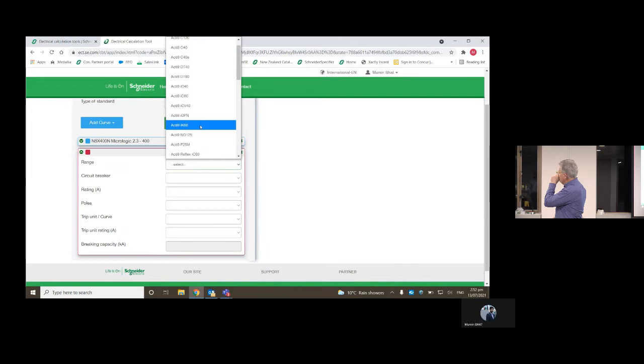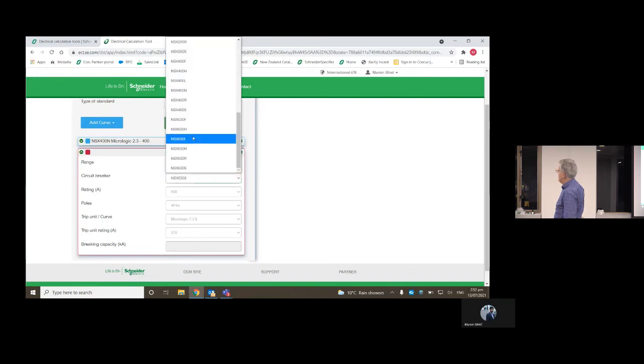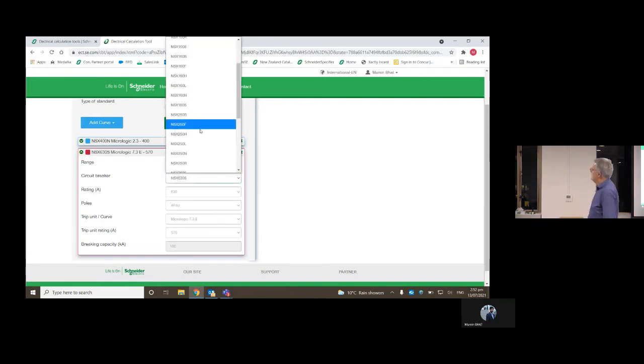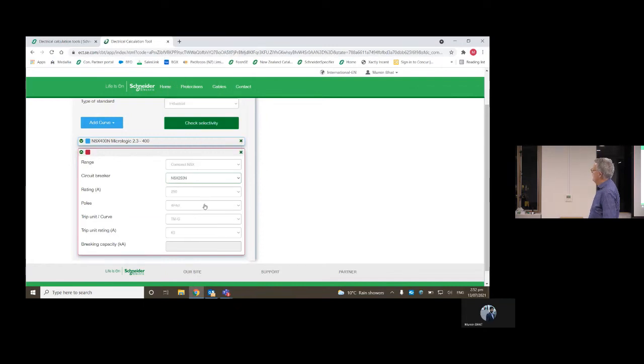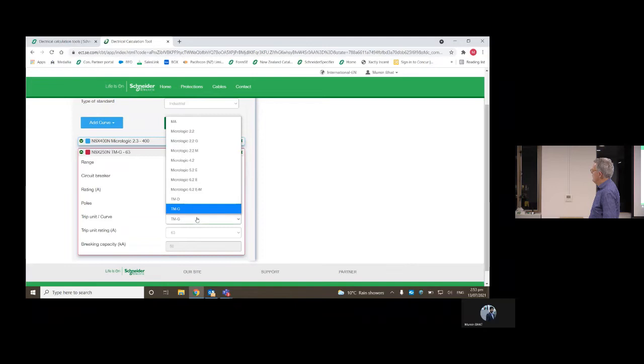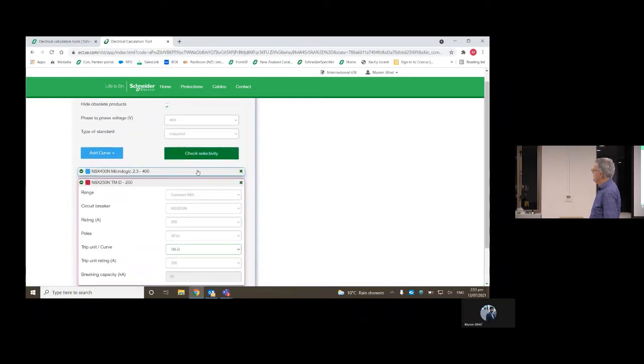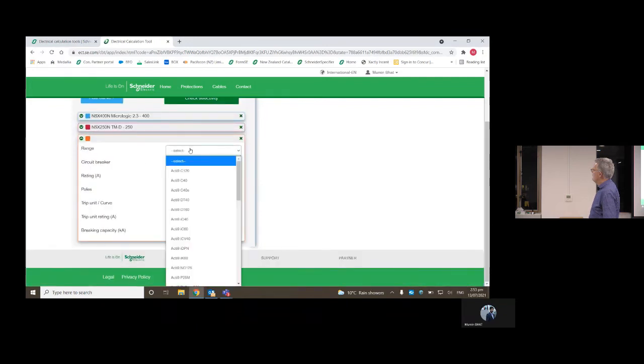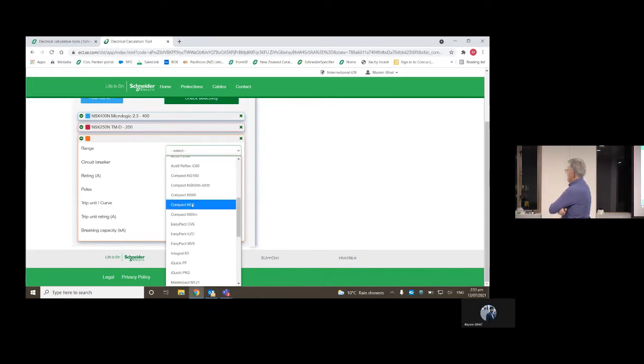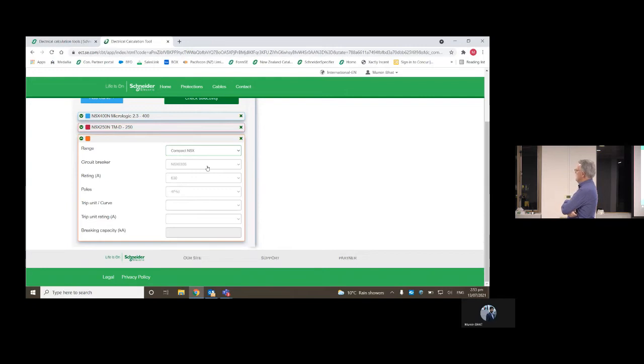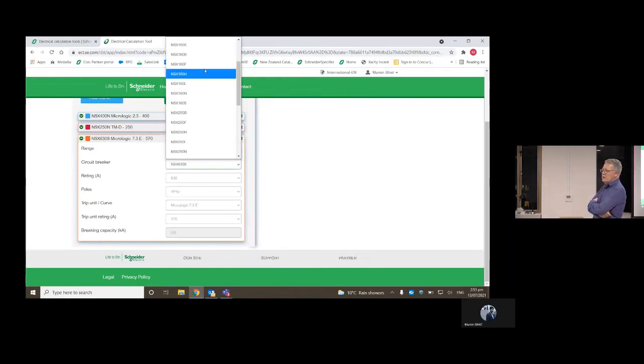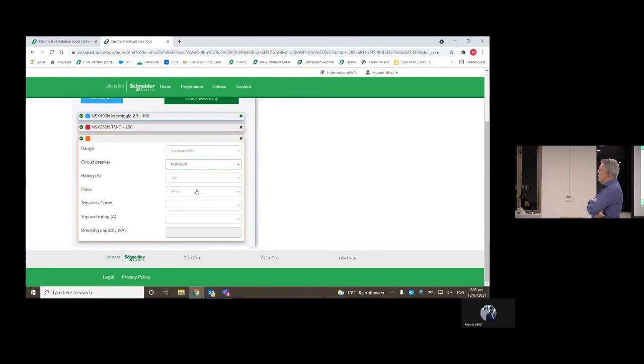Select another breaker downstream. Compact NSX, this time 250. And 250N. Change the pole rating, and we're going to put in a thermal magnetic trip. And we're going to select one more. So we're going to have 3 levels, this time a 100. So you can see it's relatively quick. I don't know if you've used it. I hope you have. If you haven't, you have a play around with it, particularly changing trip units. You'll see some differences.